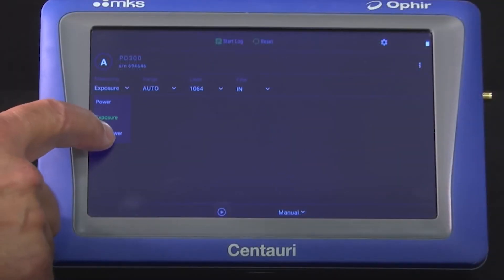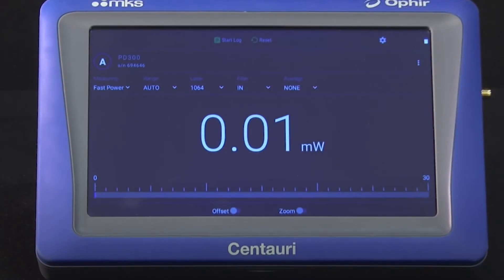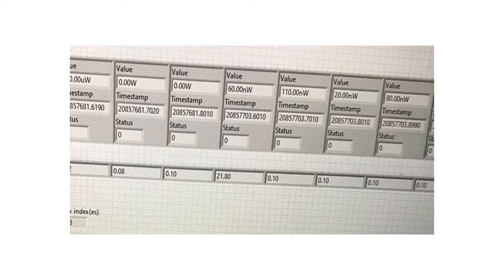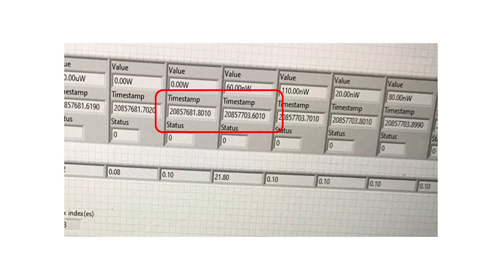The first case has to do with logging or recording of power measurements. A customer was measuring a low-power beam using a photodiode-based sensor connected to the Centauri meter. They were logging the data using the meter's fast power mode, in which the power is sampled and logged at a fast sampling rate of 10 kHz. Here you can see a snippet of the recorded data. The timestamps are in units of milliseconds, and the data points are spaced, as expected, around a tenth of a millisecond apart — and then suddenly, here it's about 22 milliseconds.